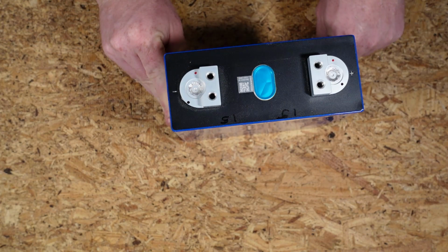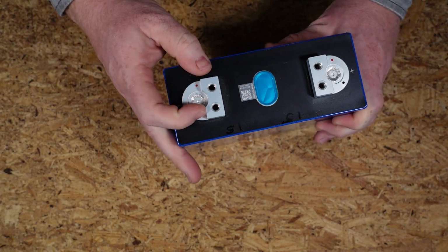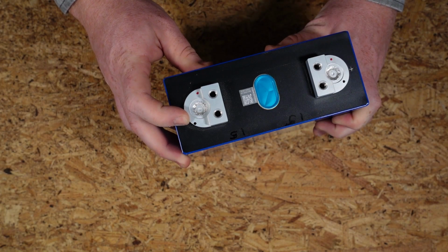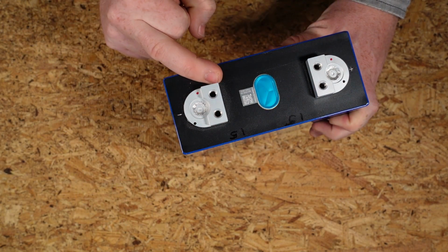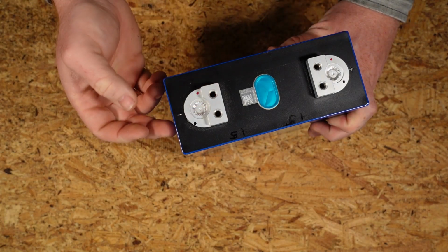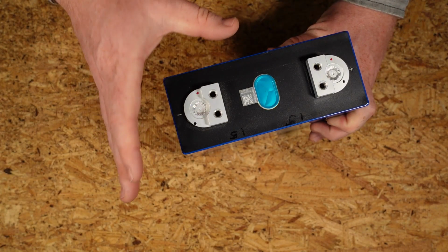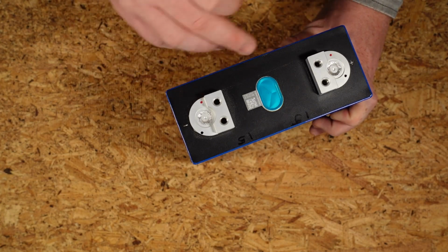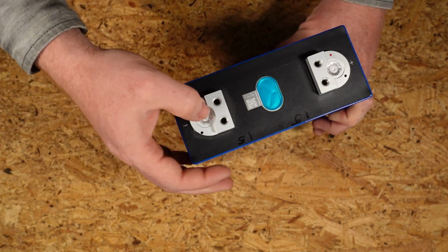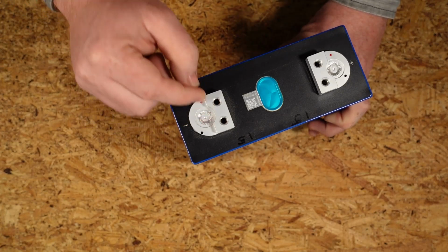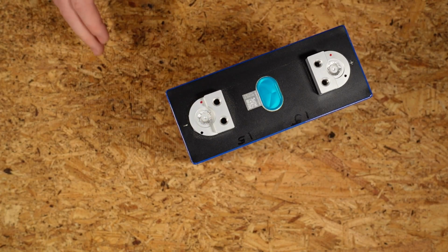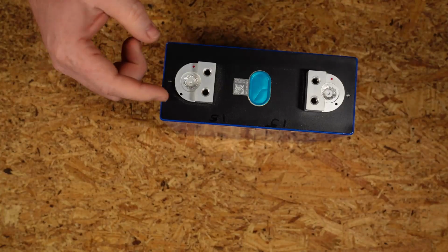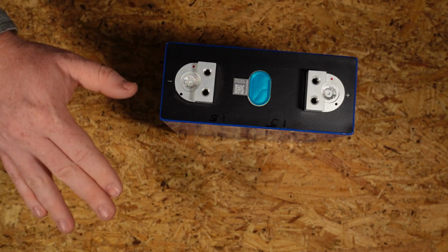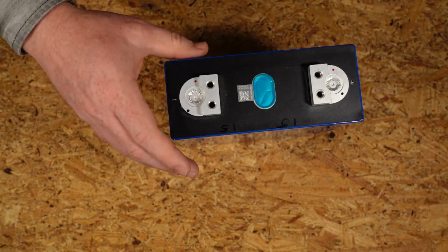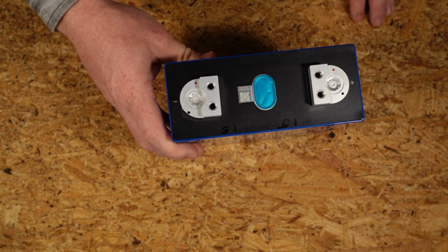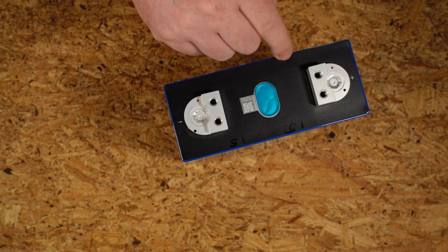So the lesson is to really make sure all your batteries are tightened to the proper specification—over-tightening them is bad. I've taken these up to 8 Newton meters and started ripping things out, so 6 is really the proper torque; I wouldn't go any higher. Just make sure these terminal tops are nice and clean before you put them in your pack. That's the lesson learned from my previous packs, and once the terminals were all finished and taken care of, I've not had the issue since. So that's the gotcha with these particular cells.